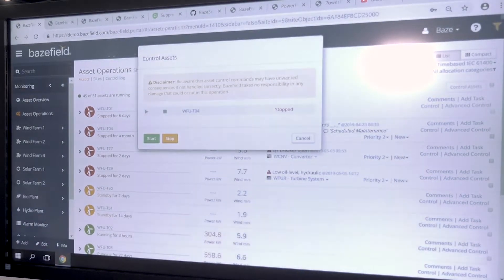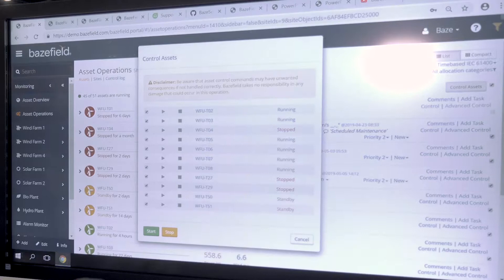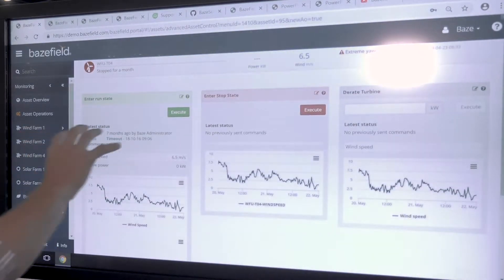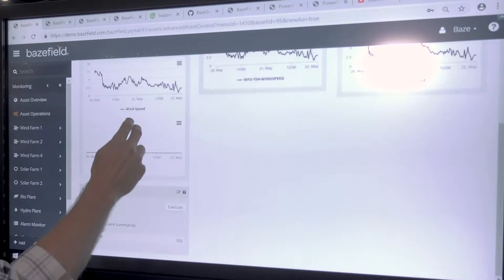For customers looking to do control, we generally recommend hosting Bazefield on your own on-premise network so you can control all the cybersecurity aspects. You can do control on a single machine or on multiple machines at once by hitting 'control assets.' For advanced control, some OEMs and SCADA systems allow Bazefield to do more than just start and stop. Any other command the SCADA allows — such as derating the turbine — can be found in advanced control. Each widget represents a distinct command we can write to the SCADA system. If you don't know what your SCADA system allows, just give us documentation and we can figure that out for you.